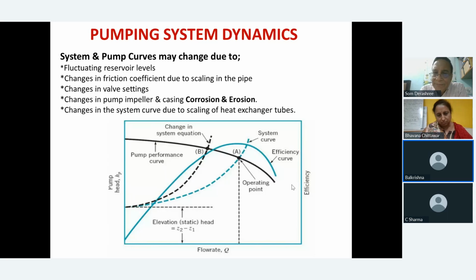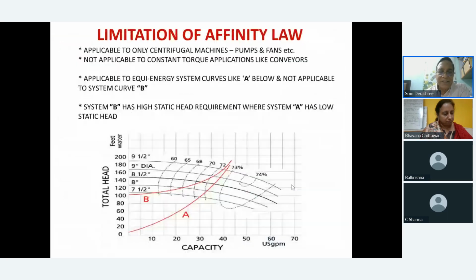So which is advisable? Does the variation in system head and the variation in discharge play a role in this decision making? See, whatever is your system requirement has to be met through that pump. But if you are having a control mechanism, that is where I had shown you this curve. If the system is flatter, then yes, VFD will not work, because the head will not be developed as much as you need. Head will fall in the square proportion.